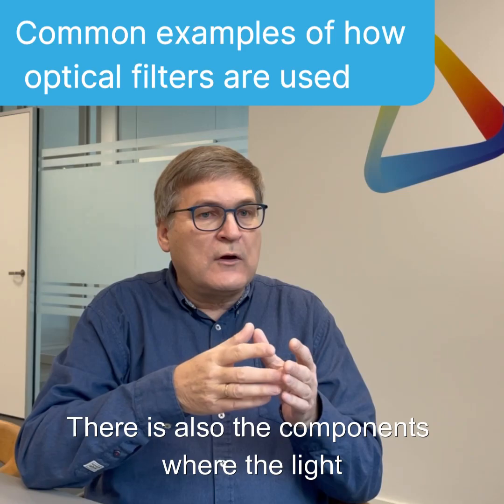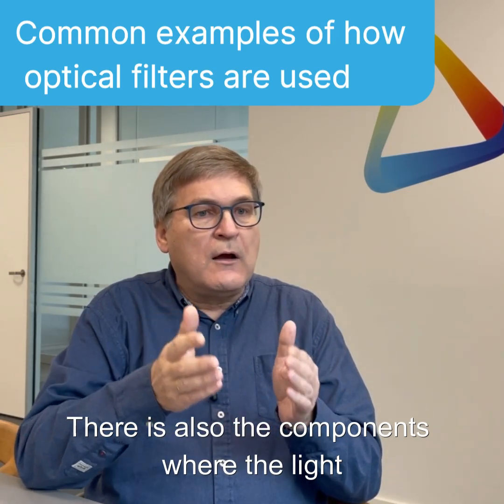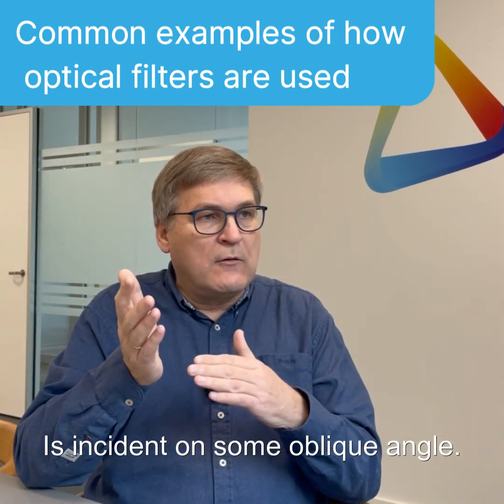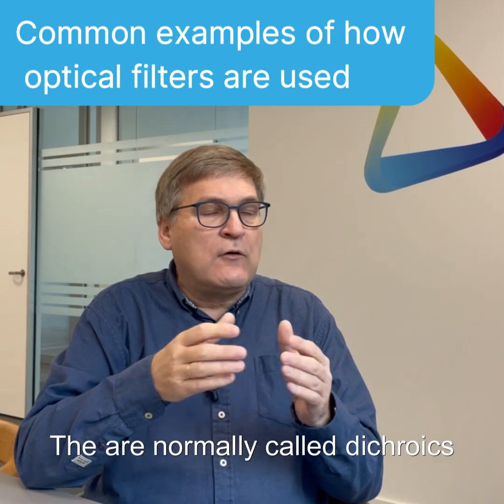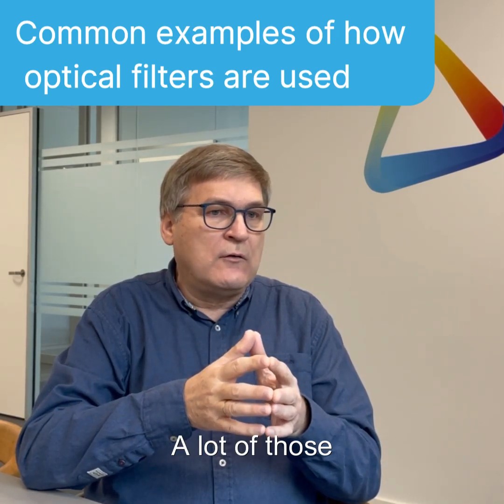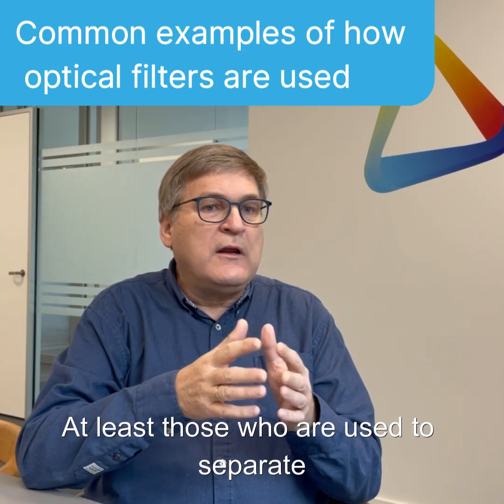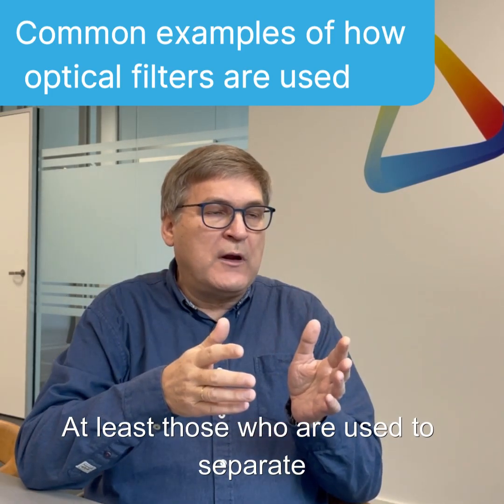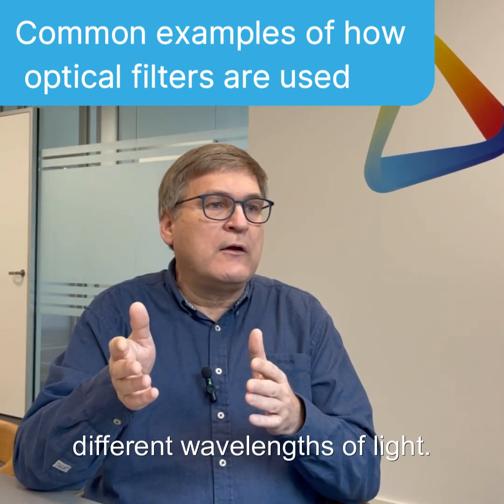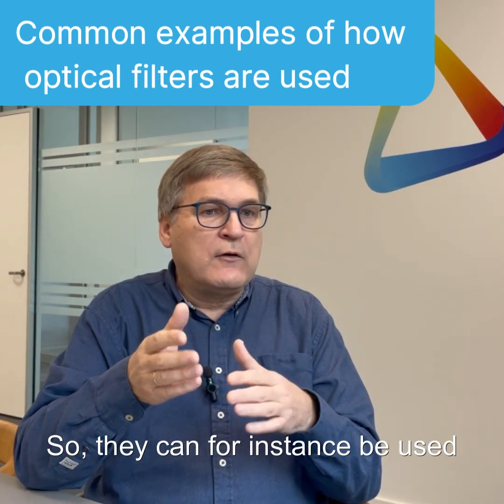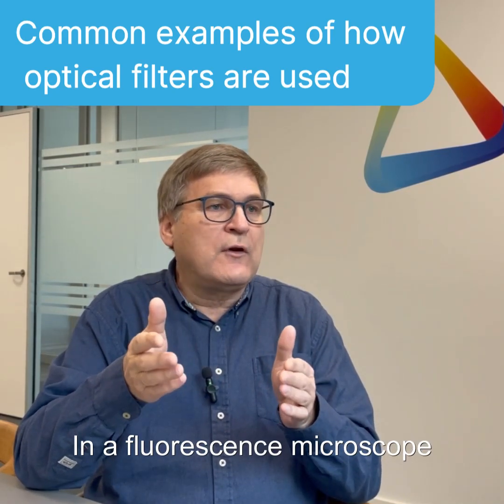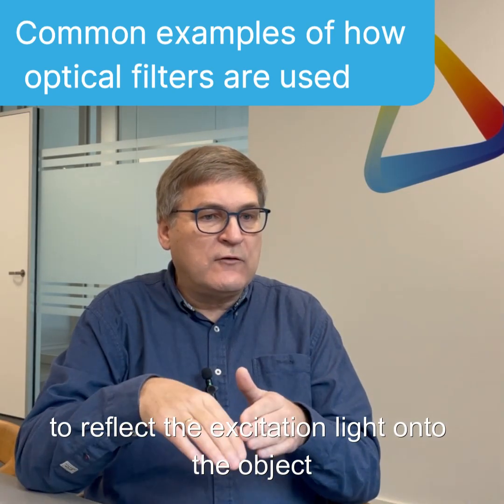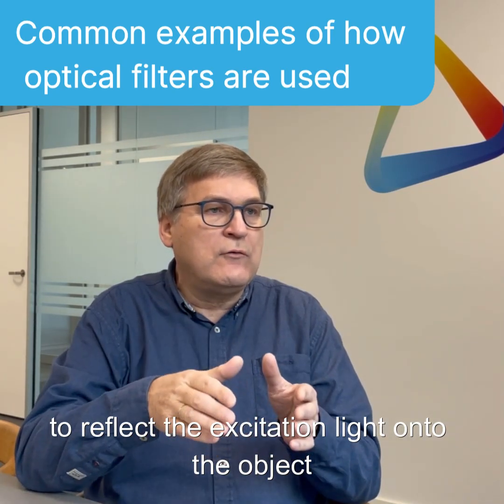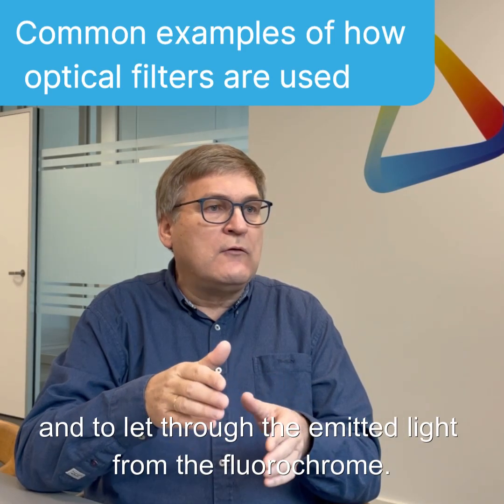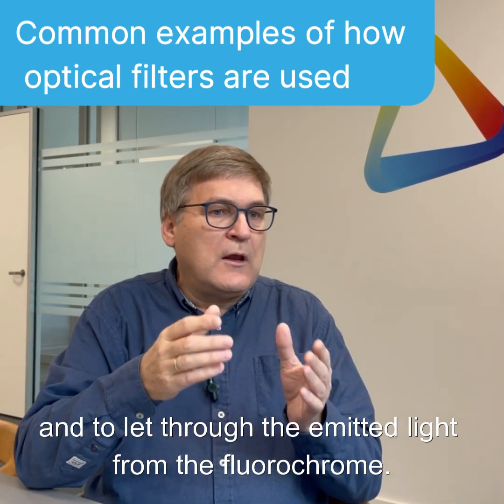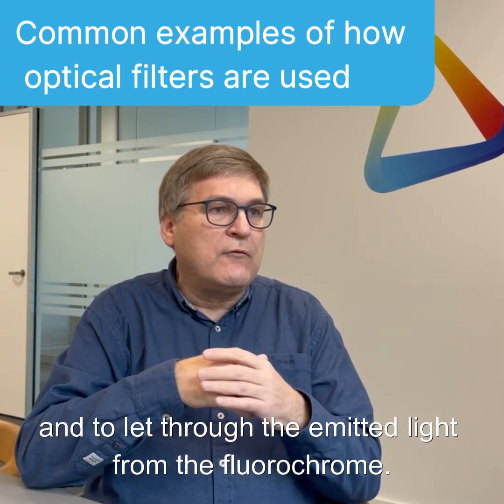There's also the components where the light is incident at some oblique angle. They are normally called dichroics, a lot of those, at least those who are used to separate different wavelengths of light. So they can, for instance, be used in a fluorescence microscope to reflect the excitation light onto the object and to let through the emitted light from the fluorochrome.